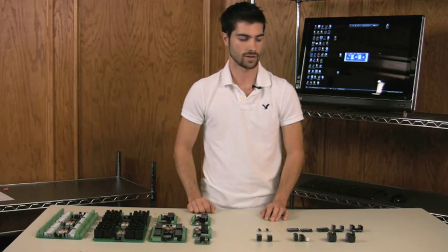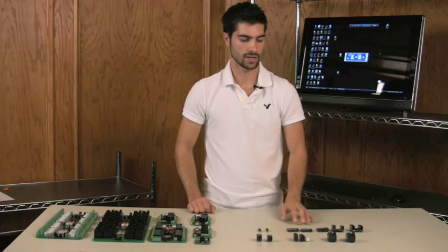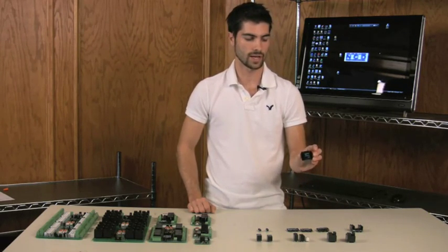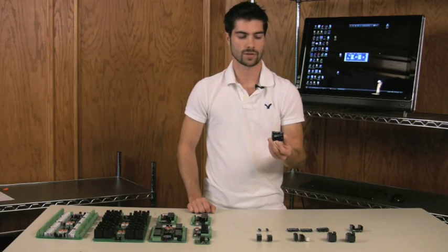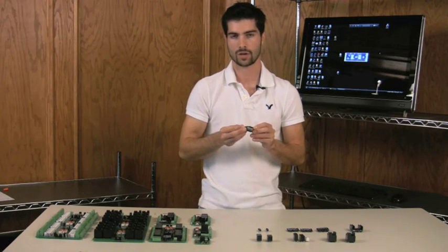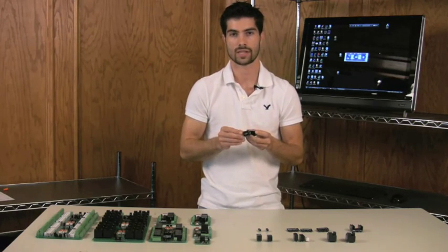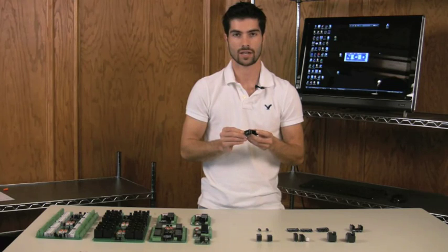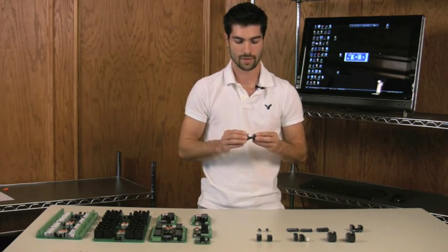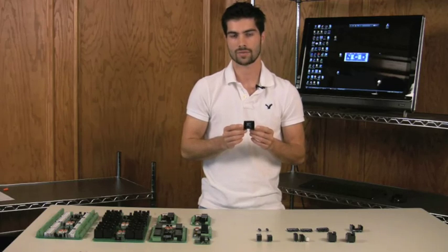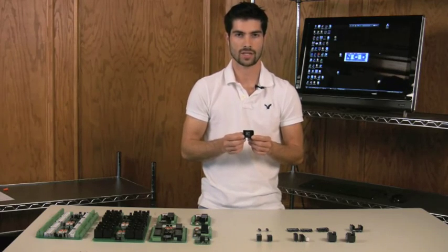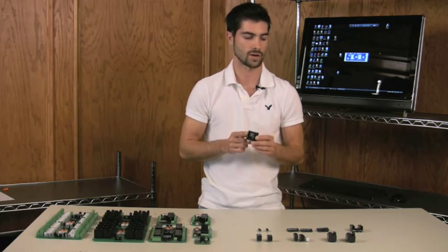When you're switching AC current, sometimes it's not a bad idea to consider solid state relays. Now these relays switch electronically, so there's no mechanical moving parts, which is kind of where the electronic industry is trying to go with solid state hard drives and things of that nature. So these are highly reliable, but only good for switching AC current. We do not offer these to switch DC current.